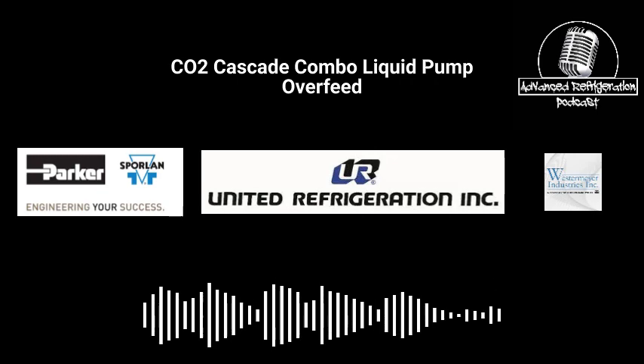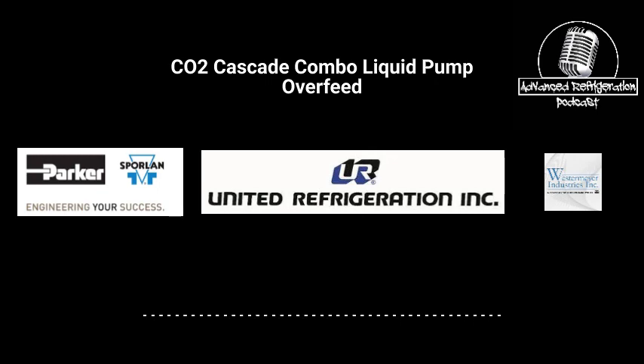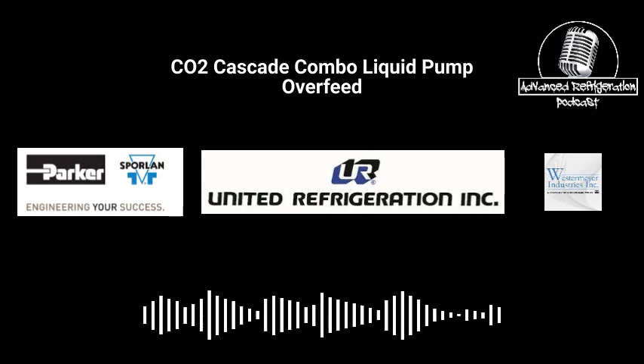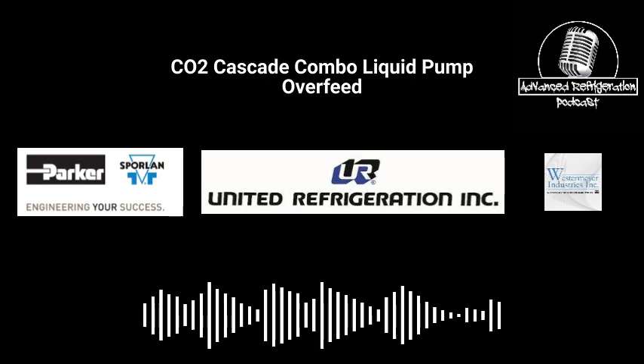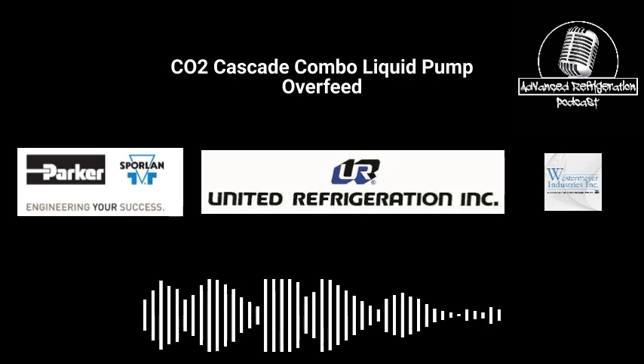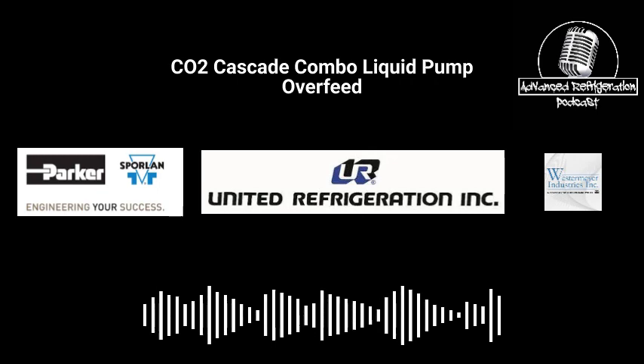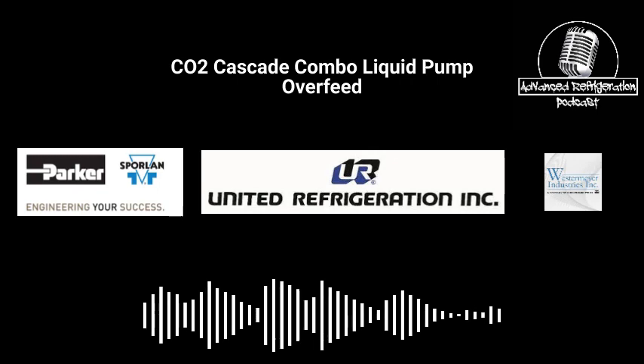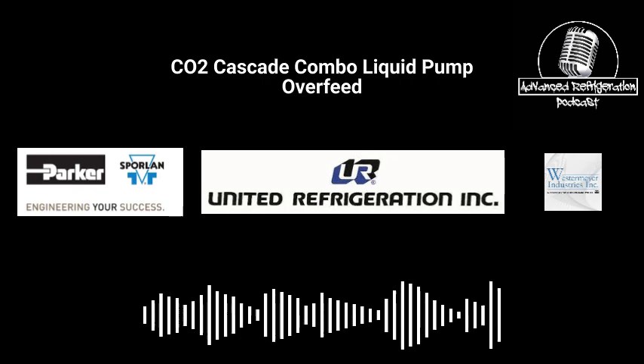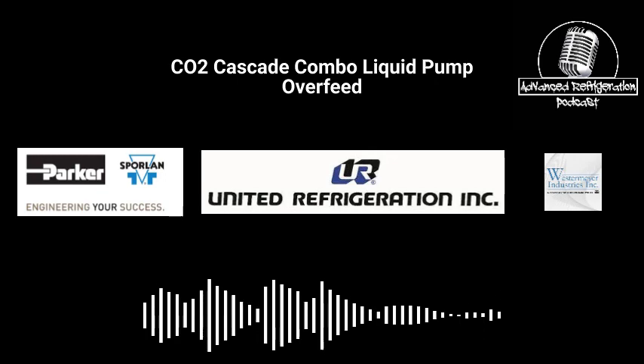All I was going to say is, for the programming for these, they use a lot of sensor controls. So you're going to have to look through, but what's really nice with a lot of their schematics is it'll actually show you an RO. It'll label what the RO is, so you know what part of the program it's for. And then there's usually a little notation. So say the de-superheater was set for a cut in at 65 and cut out at 60. That's exactly what it says on the actual schematic. So that's one thing that's really nice about this. The program kind of tells you where it is, but if you match it up with the ROs on the actual schematic, it'll help you so much in understanding that.